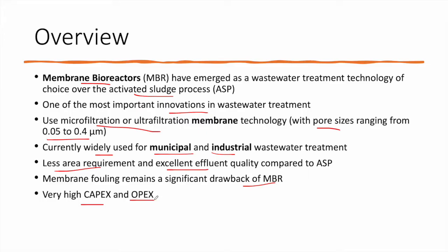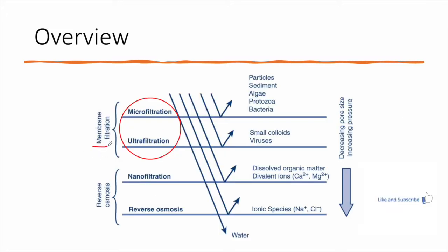In membrane filtration, we have micro-filtration and ultra-filtration — these two are involved in the MBR sheets or MBR membranes. Using these two filtration techniques, we can highly reduce colloidal particles, sediments, algae, protozoa, and bacteria, effectively disinfecting the wastewater. We can remove very small colloids and viruses, which is impossible using any traditional technique. These are usually removed in tertiary treatment. The MBR membrane can highly reduce colloidal particles as well as pathogens, achieving a very high quality effluent.